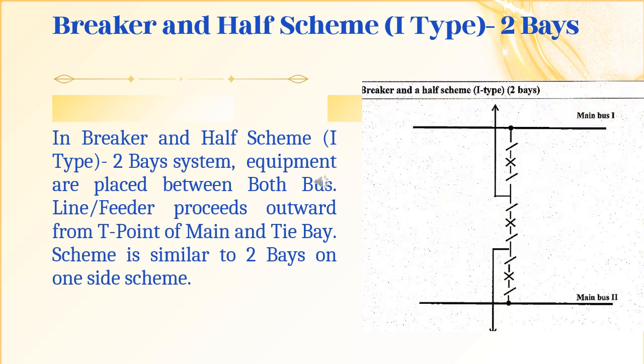In the breaker and half scheme I-type 2-bay system, equipment is placed between both buses. The line feeder proceeds outward from the T point of the main and tie bay. The scheme is similar to the two bay on one side scheme.